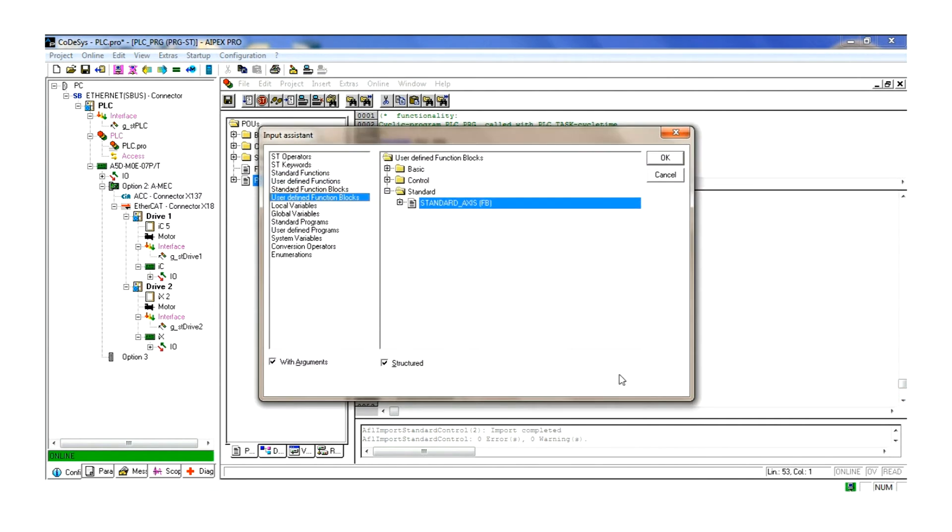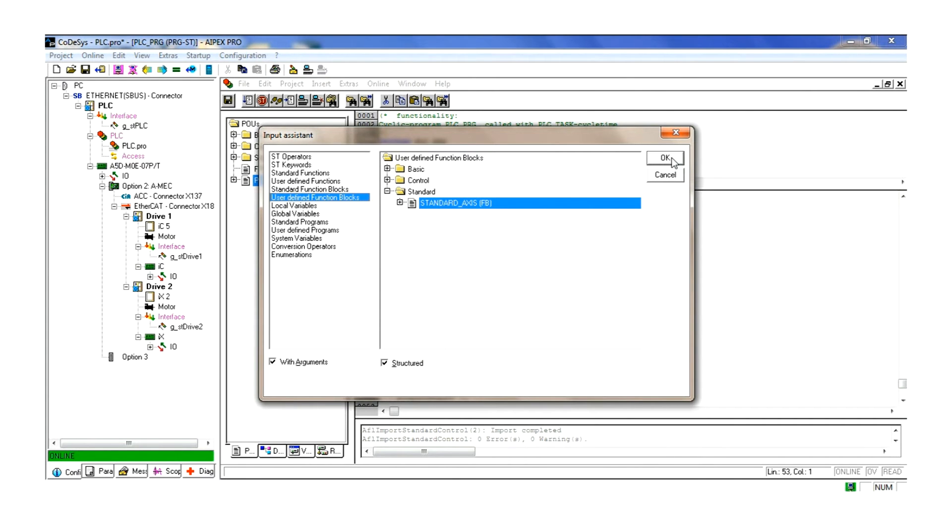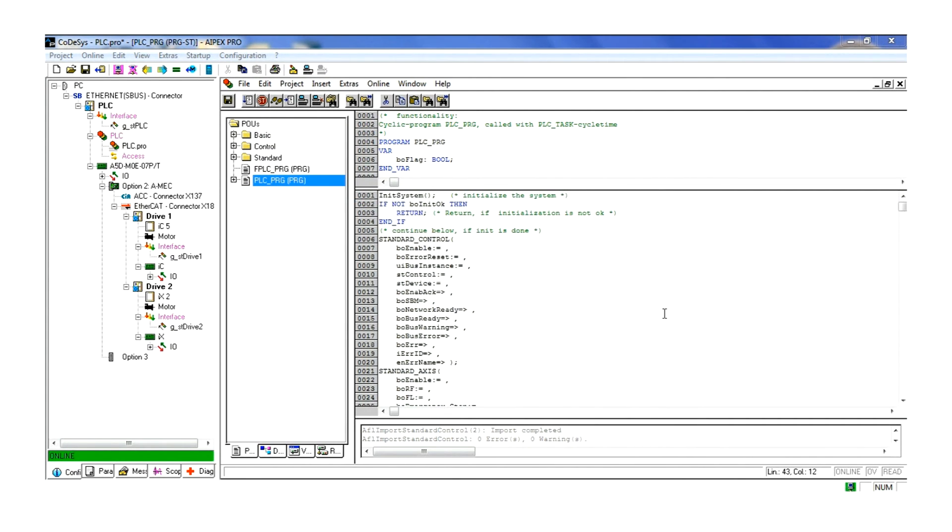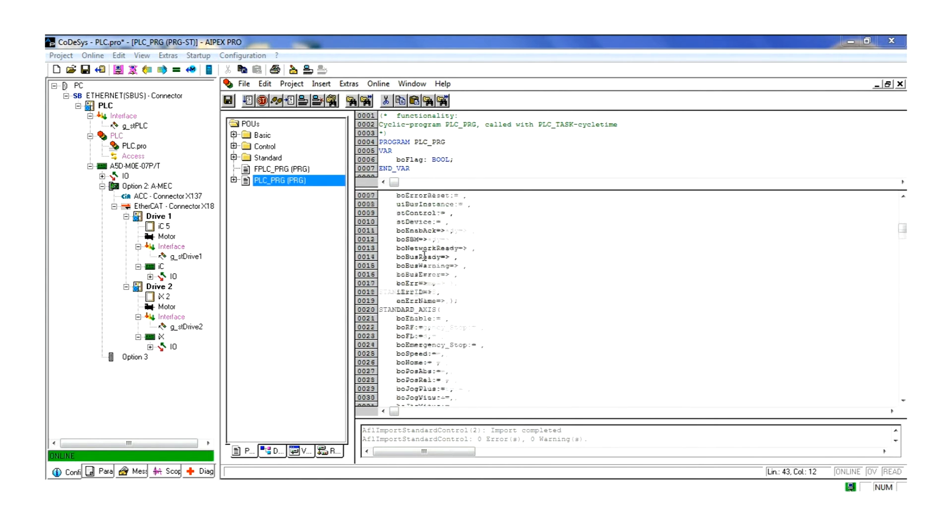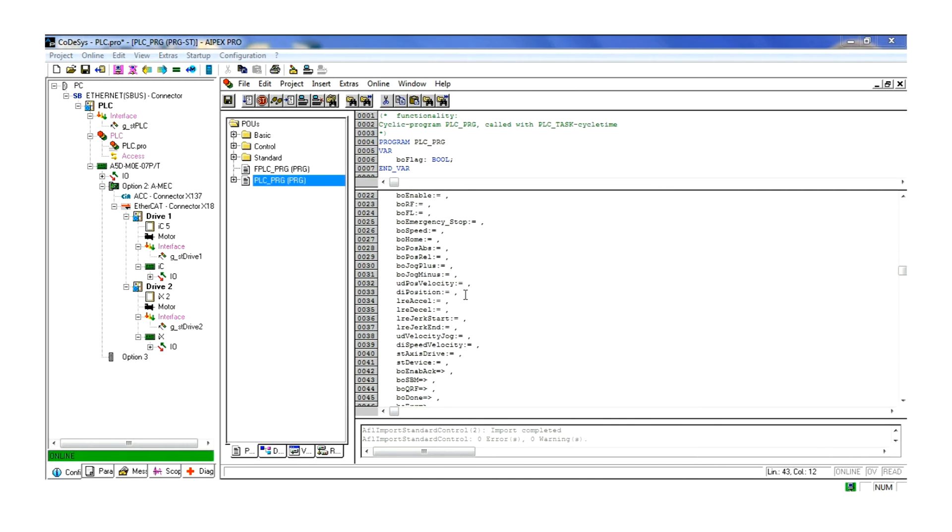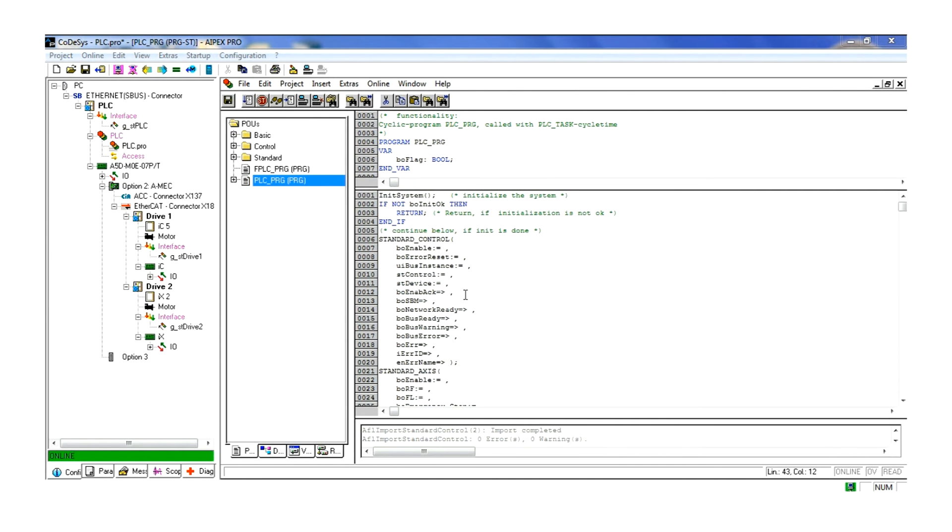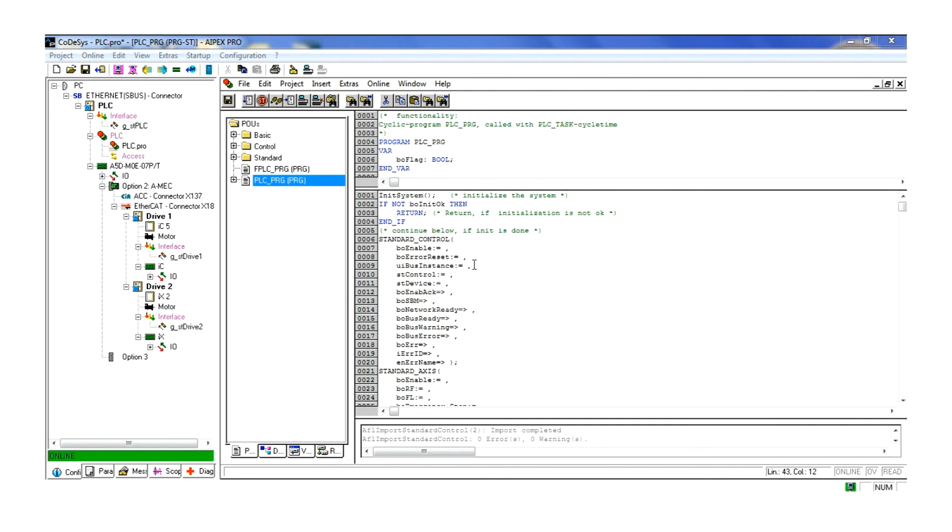FB standard control allows the monitoring of status bits and messages from the controller as well as diagnostic messages. FB standard axis allows for control of all the standard functions of the servo drive including homing, positioning, speed control, and jogging. Also it configures all of the handshake bits as well as real-time information for actual position, torque, and speed.